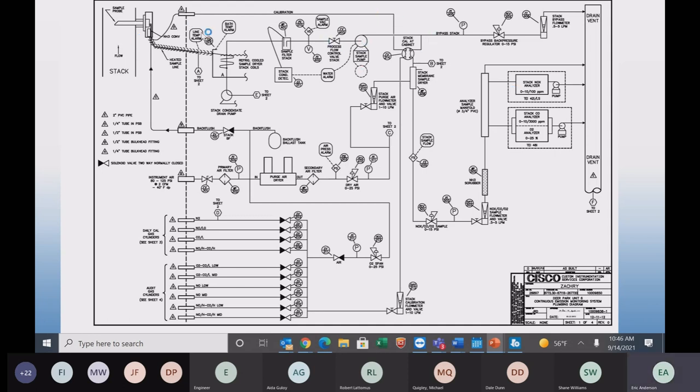Again, pressure side, we leak check the vacuum side. We're over here on the pressure side now. Here's our permeation dryer right here, membrane dryer, permeation dryer. 50 little tubes in this half inch, 2 foot tube here. So we can bypass that and see if we can get a good calibration there. Our manifold here, again, sometimes these fittings get over tightened and split the PVC. And, you know, give us more pressure into the system here. Losing pressure.